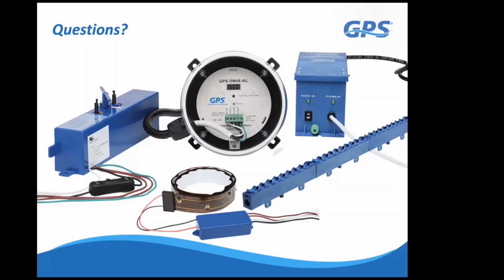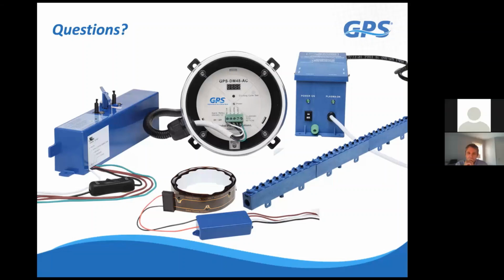But in the real world, when we get back into levels that we're going to see in larger spaces, like in hospitals and schools, we're generally around 5,000 ions per cc. So that rate's going to come down slightly. It's not going to be the 99.4 in 30 minutes. It might be 94 or 95% in 30 minutes. But we'll know because we're continuing the testing as we speak.